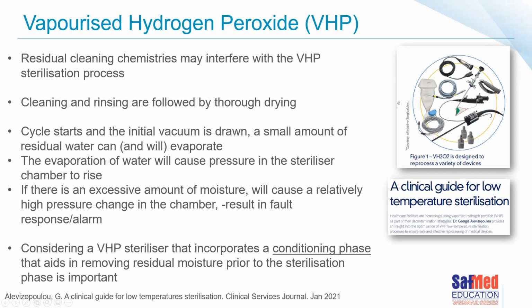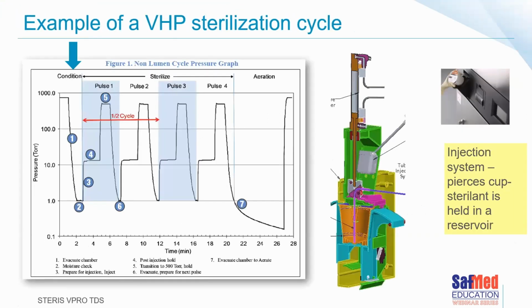You may realize, of course, that if we're using steam the whole time, we tend to not be as focused on drying our instruments that much. But when you're using vaporized hydrogen peroxide, you do need to make sure that your instrument is nice and dry before you start. Here's an example of a vaporized hydrogen peroxide sterilization cycle that does include a conditioning phase. Here, the machine will draw its initial vacuum. It pauses for a minute and does a moisture check. If the moisture level is still too high, it draws another vacuum again in an attempt to try to reduce the moisture before we're actually injecting the sterilant.